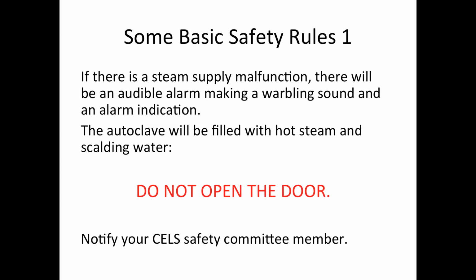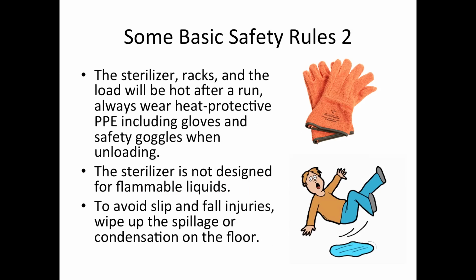Autoclaves use live steam, hot water, and they're very hot, which you know already, but it's worth repeating. Now, on our CELS autoclave, if there is a steam supply malfunction, you will hear an audible alarm making what's been described as a warbling sound. If that happens, the autoclave may be filled with hot steam and scalding water, so it's common sense, but don't open the door. Notify your CELS safety committee member to deal with that issue.